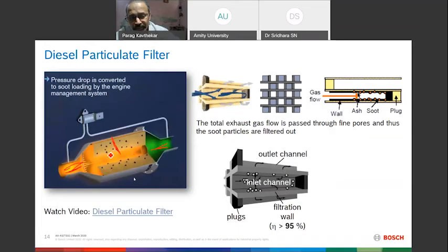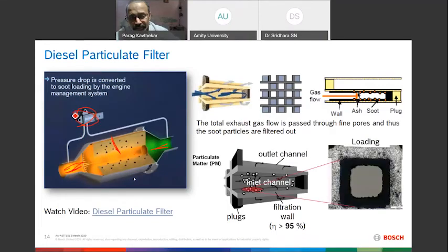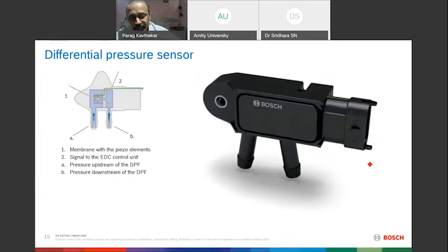To understand the clogged area, we have a sensor for partial differential pressure. With the help of this pressure difference, before and after the filter, we come to know the clog level, as the filter gets clogged with a carbon layer, and the entire box fills with carbon coating. This sensor helps us understand that area.